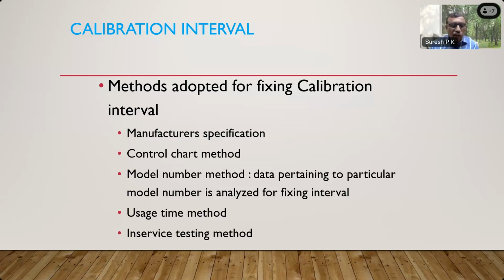Suppose I tell you an example. Suppose you have a flow meter which measures, say, 50 tons of naphtha per day. The naphtha cost is something like 70,000 per ton. So if you have 1% inaccuracy, imagine what loss you are going to incur. Your flow meter is showing minus 1% in your measurement. If you are measuring 20 tons of naphtha, minus 1% is 0.2 tons per day. Take 30 days, it is 6 tons per month. That into 70,000 rupees is too high. You take it for a year. So the amount of inaccuracy you can accommodate will basically depend on the calibration interval.